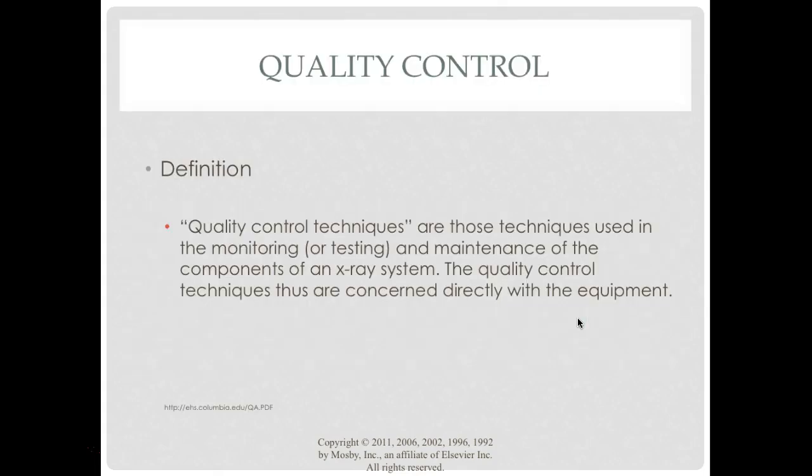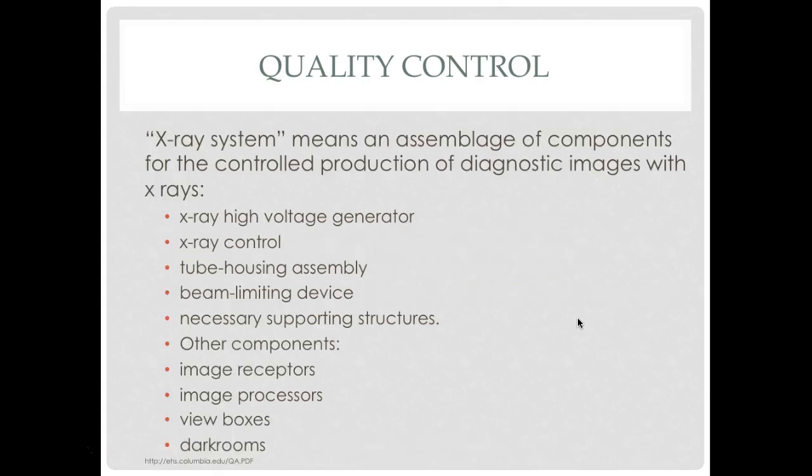So quality control, here's your definition. Techniques used to monitor or test and maintenance of the components of an X-ray system. The quality control techniques thus are concerned directly with the equipment. So quality control is equipment.